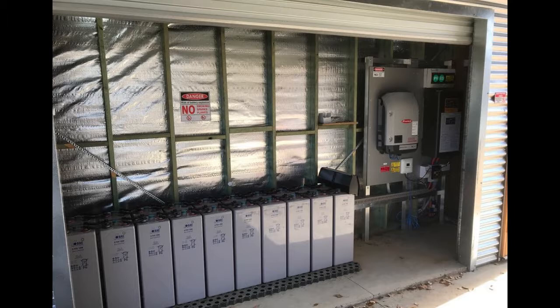But generally our recommendation, lithium, lead acid, most batteries, they don't like big temperature fluctuations. They don't like really hot conditions. They don't like really cold conditions. So anything you can do, on a concrete slab with lead acid, you really need to isolate it from the slab, but the slab will help to maintain the constant temperature in the battery room. If you can insulate it, ventilate it, normally we'd locate it in the south side, southeast corner of a shed or something. If it's going inside a shed, stay away from those north or west walls that tend to get a lot of heat.